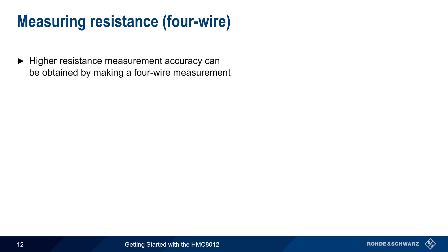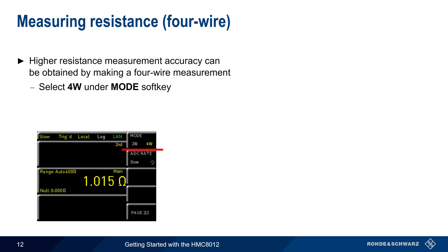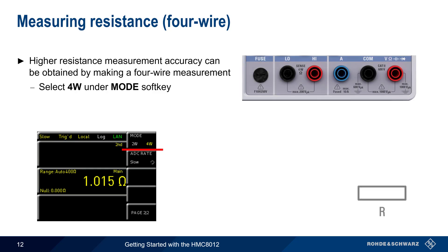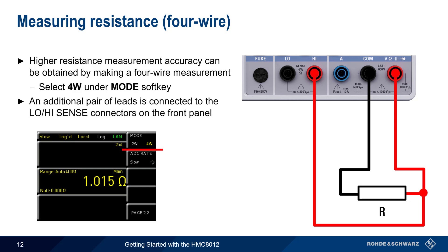Greater measurement accuracy can be obtained by making a 4-wire resistance measurement. This is done by changing from 2-wire mode to 4-wire mode under the mode menu. In addition to the standard 2-wire connection, another pair of leads is connected from the low-high sense connectors to a point close to the measured resistance. In this way, the HMC can compensate for the resistance in the measurement leads, improving accuracy for very low resistances.